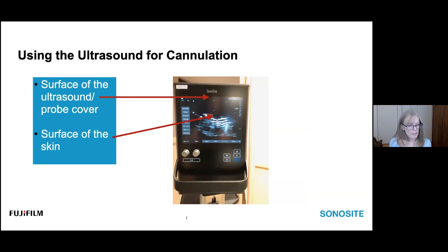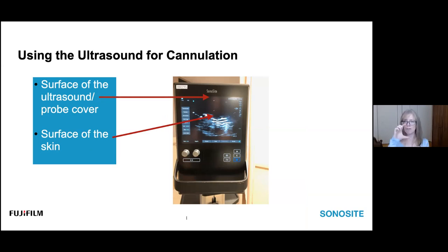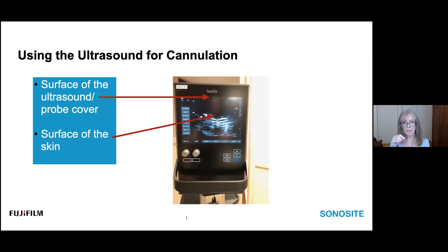When using a lot of gel, the top of the screen is not the surface of the patient's skin. The gel creates distance, so the top arrow indicates the top of the image while the bottom arrow indicates the actual surface of the patient's skin. This matters when determining vessel depth, which affects the angle of approach for cannulation.